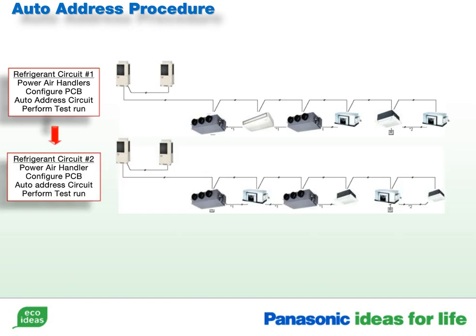If the test run has proven that the refrigerant circuit is operating properly, repeat the process until all of the circuits have been addressed and tested. Both refrigerant circuits have been addressed and are operating properly.